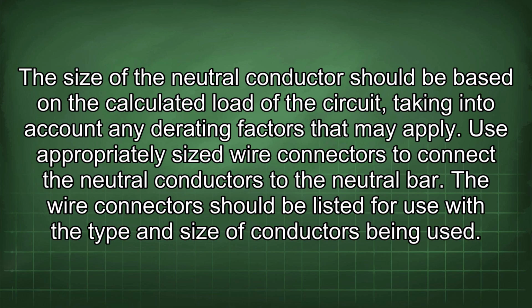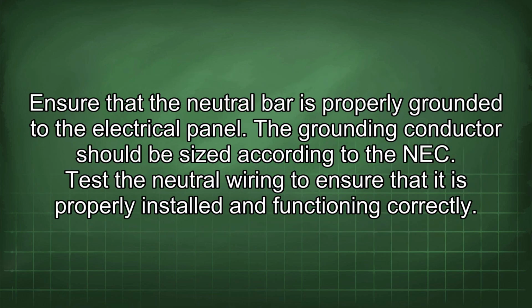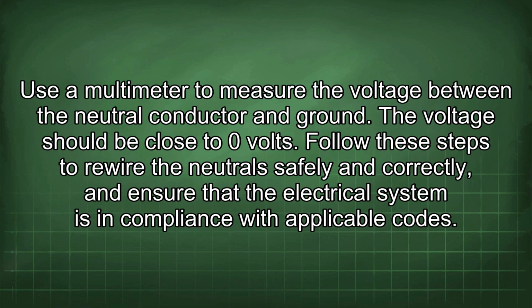Use appropriately sized wire connectors to connect the neutral conductors to the neutral bar. The wire connectors should be listed for use with the type and size of conductors being used. Ensure that the neutral bar is properly grounded to the electrical panel. The grounding conductor should be sized according to the NEC. Test the neutral wiring to ensure that it is properly installed and functioning correctly. Use a multimeter to measure the voltage between the neutral conductor and ground. The voltage should be close to 0 volts.